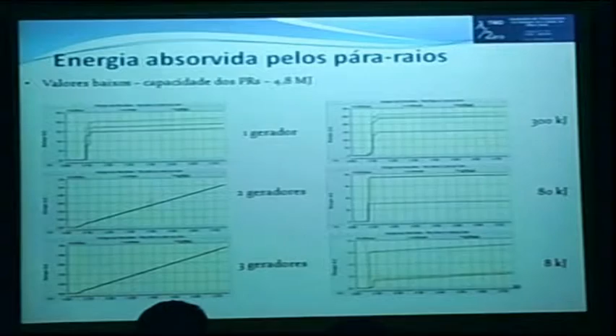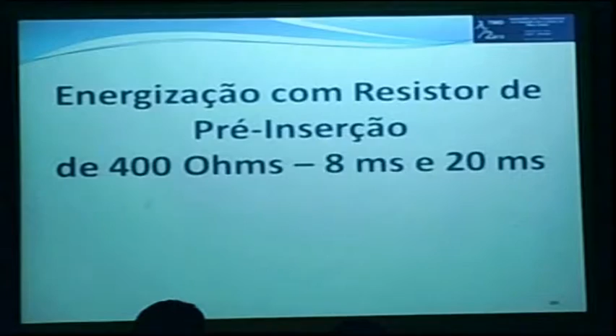The surge arresters are located at the substations. So here I have the energy on the surge arrester. I cannot actually read it, but this would be the beginning of the line and the end of the line. At the end of the line I have 300 kilojoules, which is very low. The capacity is 4.8 megajoules. So the surge arrester is not actually working.